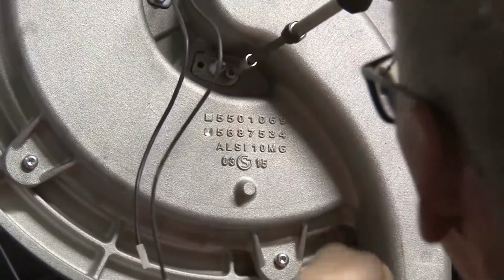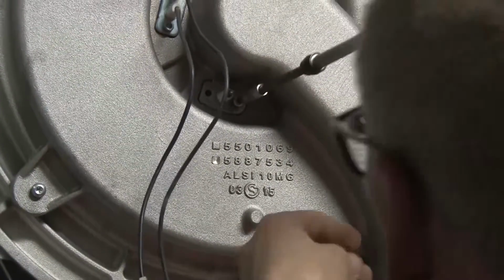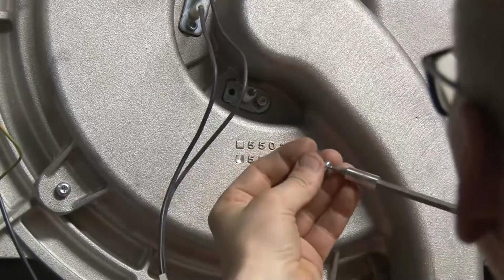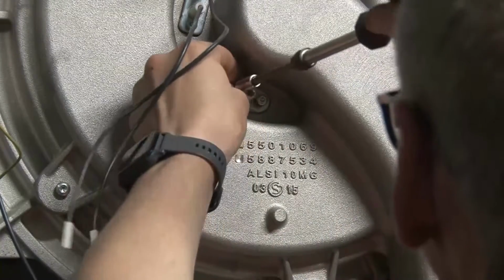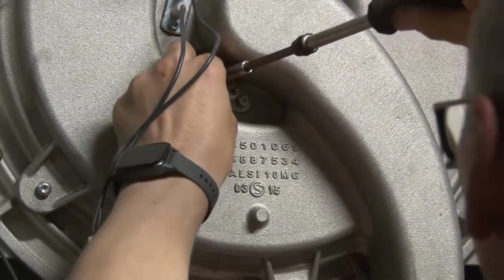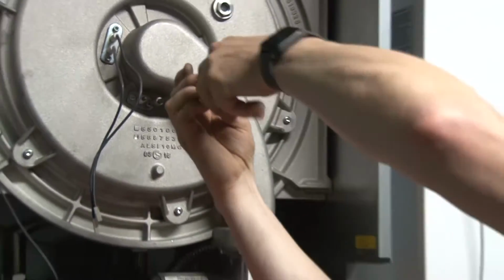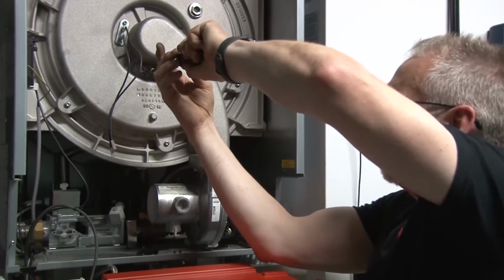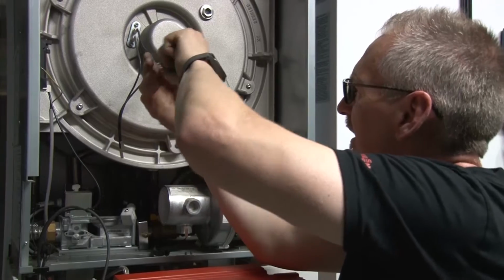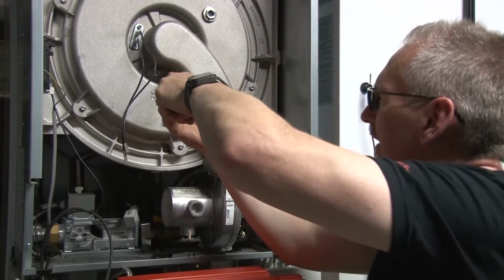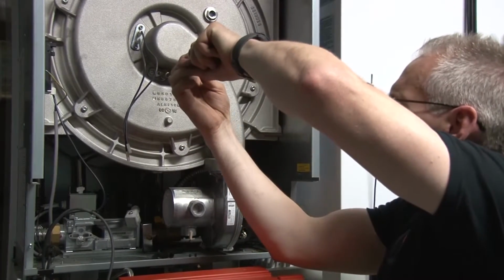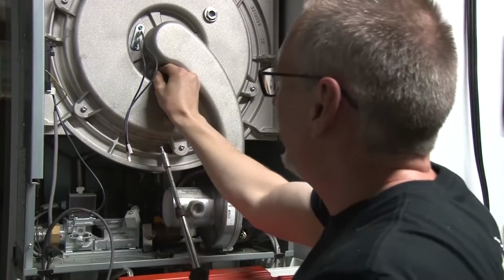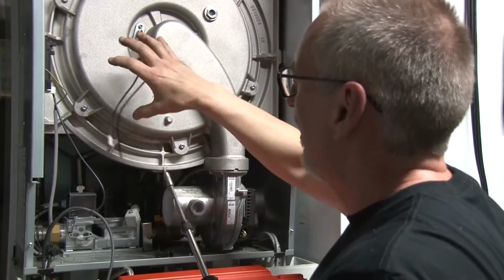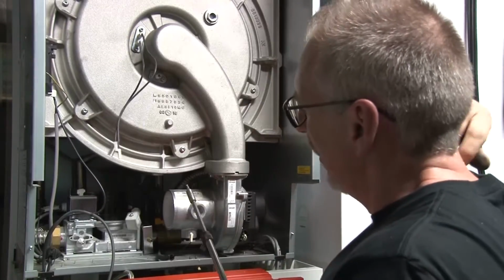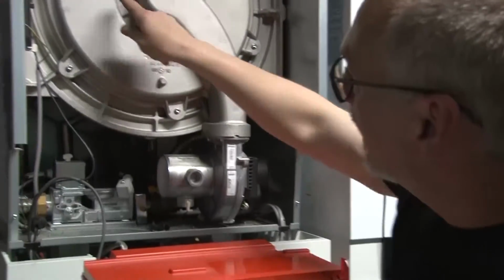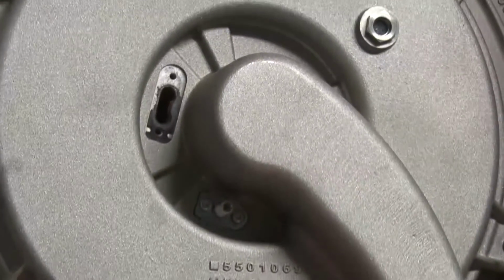All right, so we'll just torque these bolts in. And I'm not going to tighten them down until I have both of them in because you don't want to cross thread these. I'm going to soak this down a little bit when we fire this fella up to make sure that there's nothing leaking out of here, just to ensure that that gasket still had its integrity. Important to do that stuff. Anytime we open up anything here, we want to make sure that when we close it back up, we're not having an issue. So you see this electrode here, the gasket fell out.